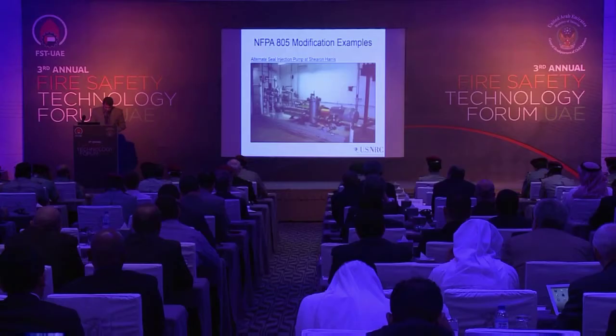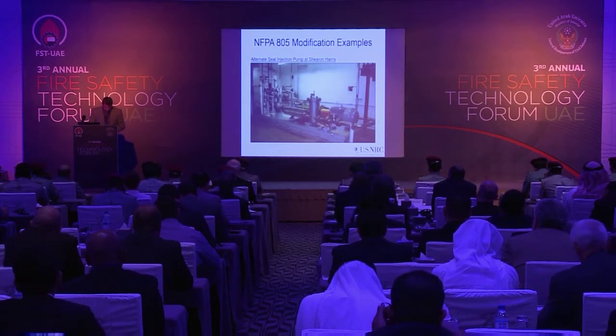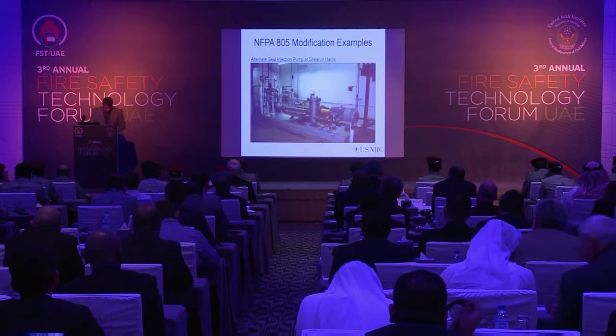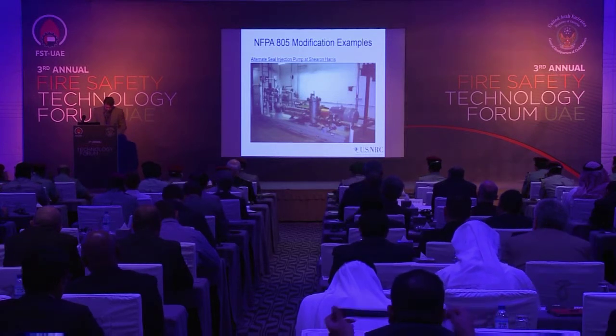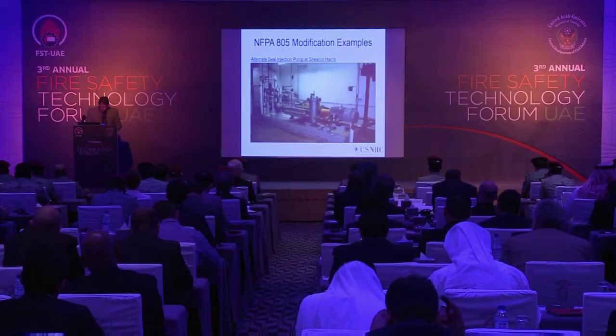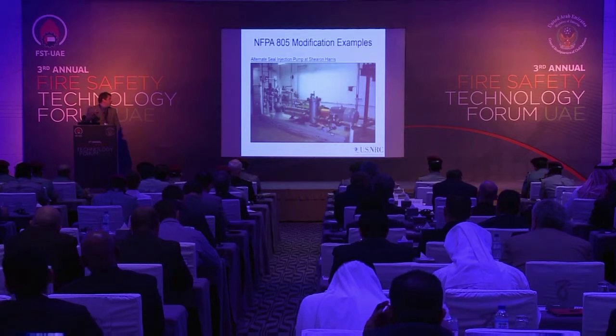The total modification included the pump and a completely independent diesel generator, a boric acid storage tank, suction and discharge piping, and controls to make the alternate seal injection system fully automatic, so that upon a loss of reactor coolant pump seal injection, the new diesel generator and associated pump would automatically start without the need for operator intervention and provide reactor coolant pump seal cooling. The utility reduced its fire risk considerably with this alternate seal injection system and with the other modifications made for NFPA 805, which are shown on the next slide.